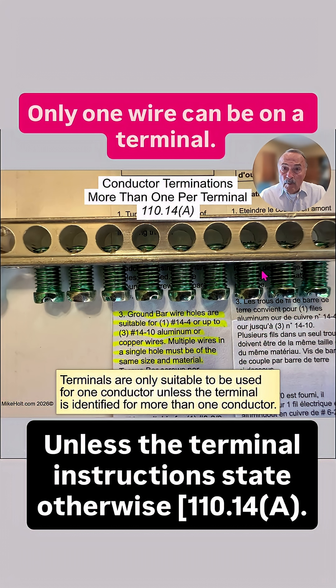And here's an example of a terminal bar — the instructions indicate three #14 to 10 gauge aluminum wire or copper conductors. And when you have multiple wires on a single hole, they shall be of the same size and of the same material.